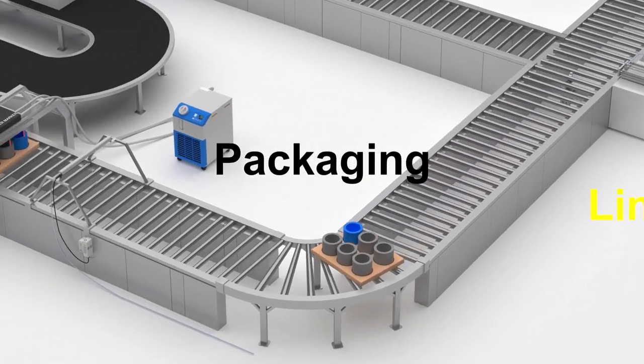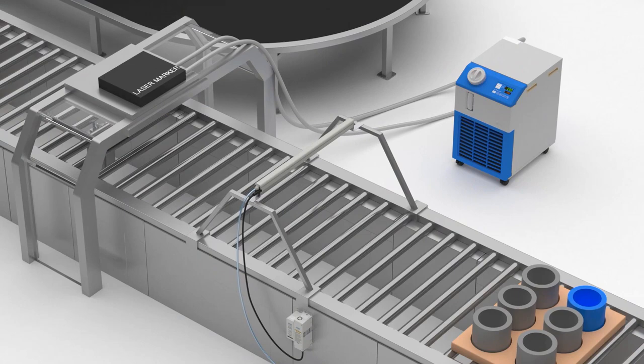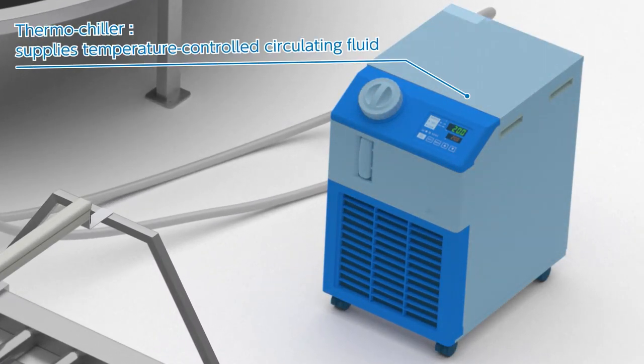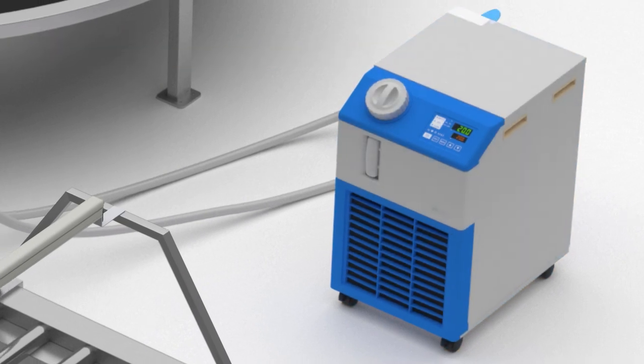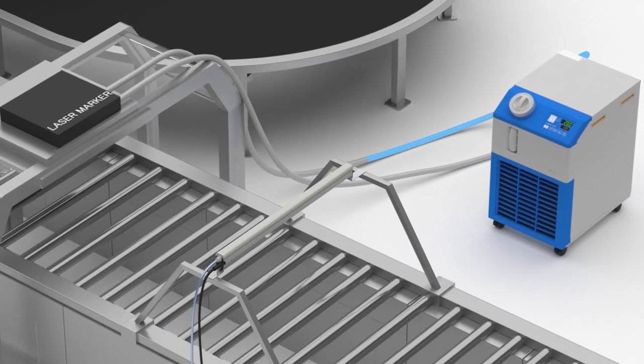The workpieces that are distributed to the second packaging line will be laser marked. A thermochiller controls the temperature of the circulating cooling fluid for the laser. After the circulating fluid discharged from the thermochiller has been heated by the laser, it returns to the thermochiller, and the circulating fluid is controlled to remain at a set temperature by the refrigeration circuit.